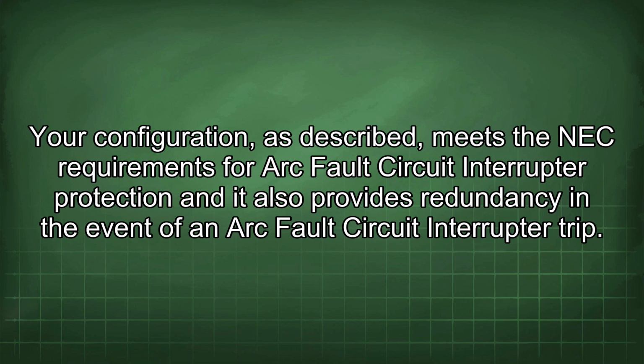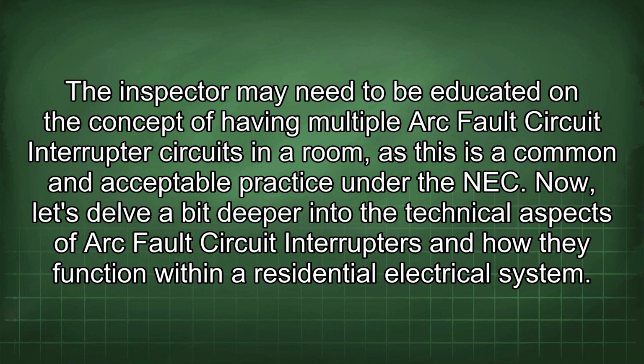Your configuration, as described, meets the NEC requirements for arc fault circuit interrupter protection, and it also provides redundancy in the event of an arc fault circuit interrupter trip. The inspector may need to be educated on the concept of having multiple arc fault circuit interrupter circuits in a room, as this is a common and acceptable practice under the NEC.